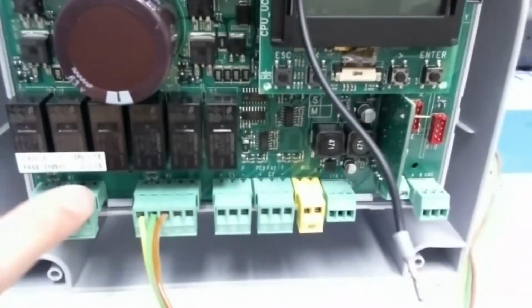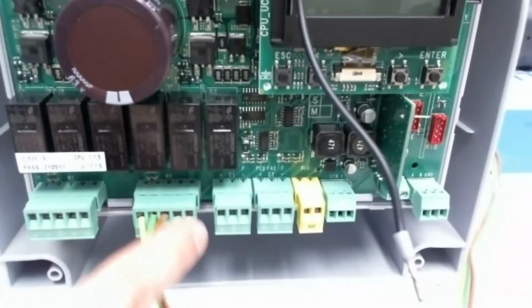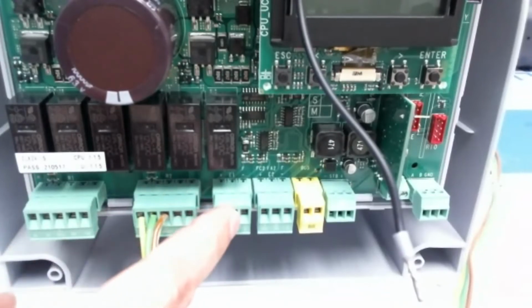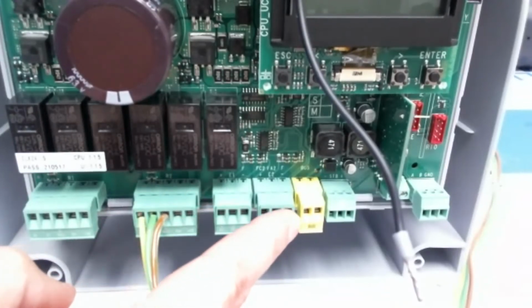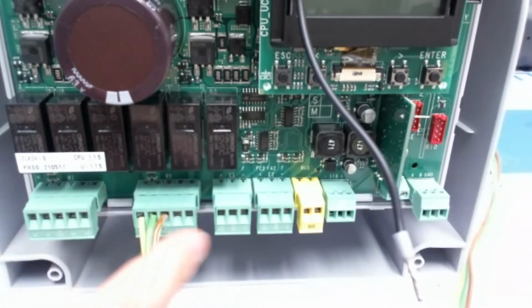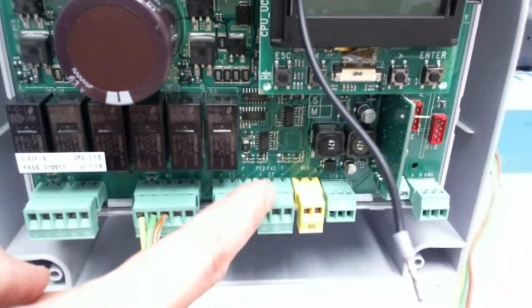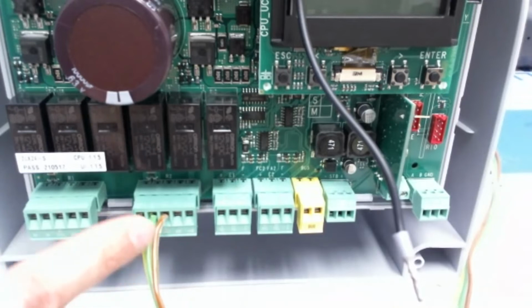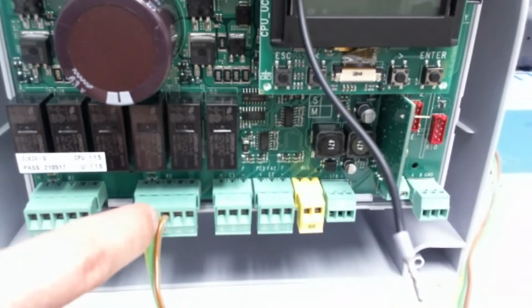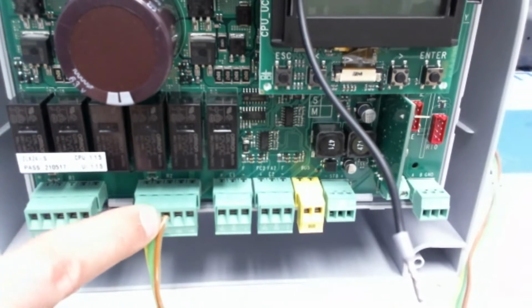This is where you connect motor number 1, and this is where you connect motor number 2. This is the limit switches for number 1 and limit switches for number 2. In this case, this operator doesn't use limit switches, so nothing is connected there. This one only has M and N, which is the motor itself, and this third one is an encoder, which only has one cable.